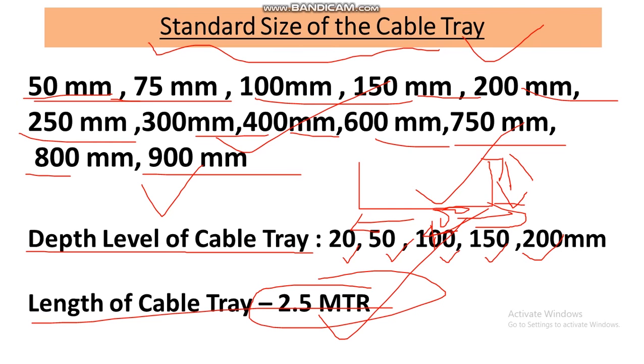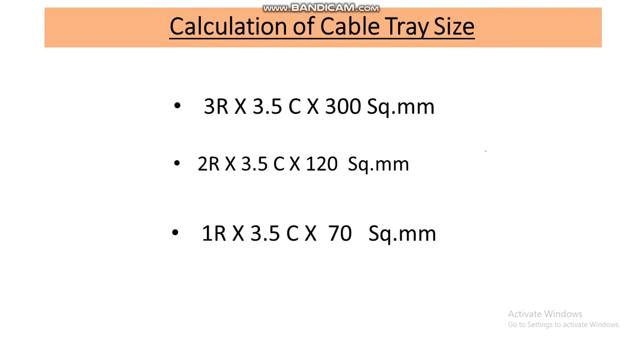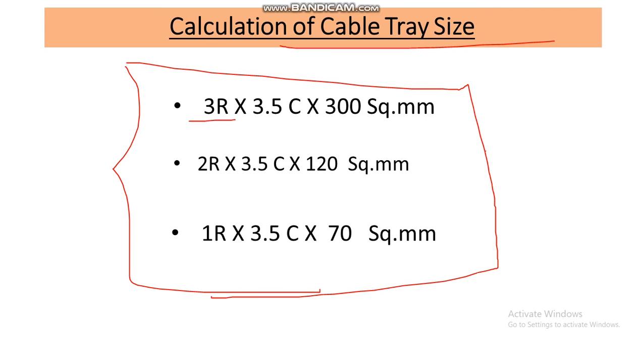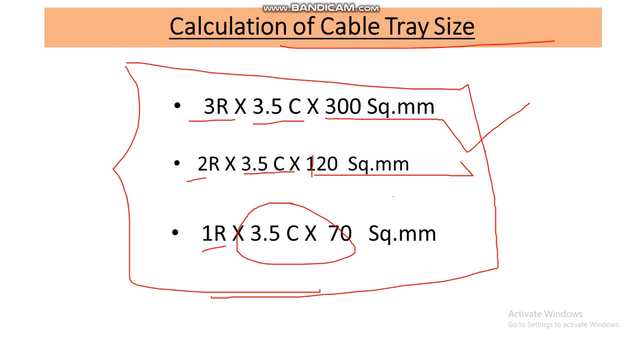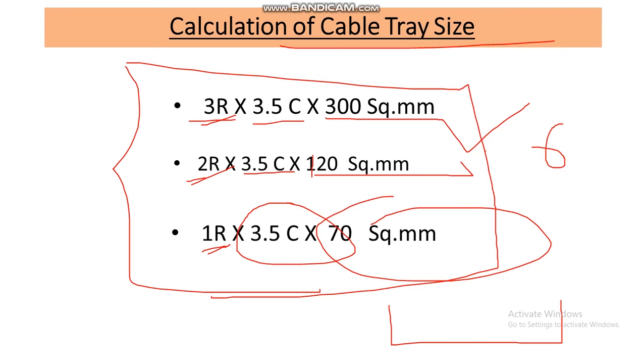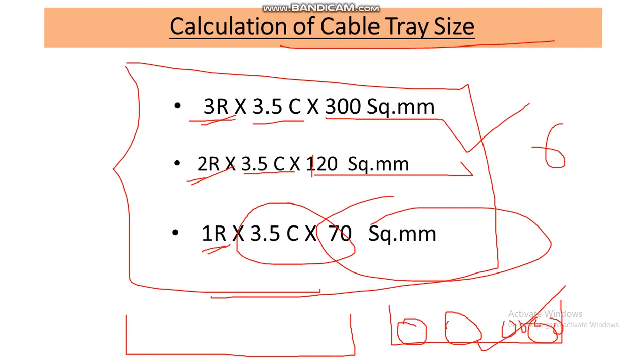Now let's come to the calculation part. We are going to calculate the cable tray size for this cable system. We have three runs of 3.5-core 300mm² cable, two runs of 3.5-core 120mm² cable, and one run of 3.5-core 70mm² cable — six cables total. These six cables will be laid in the cable tray, and remember we have to keep space between two cables during laying.